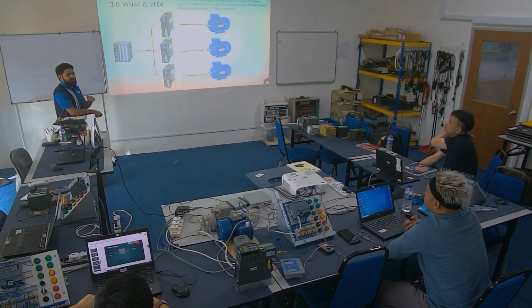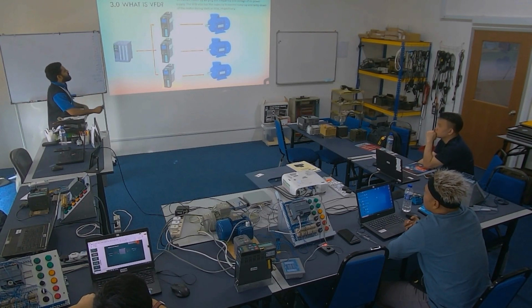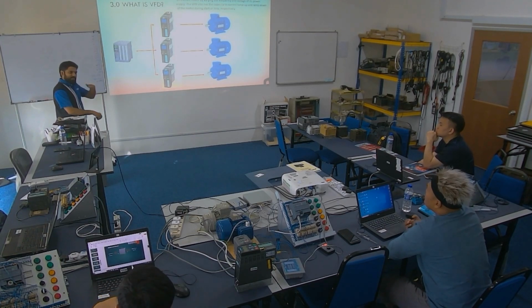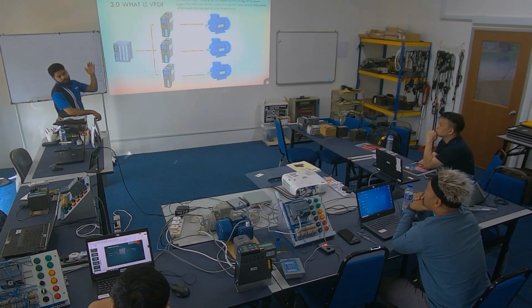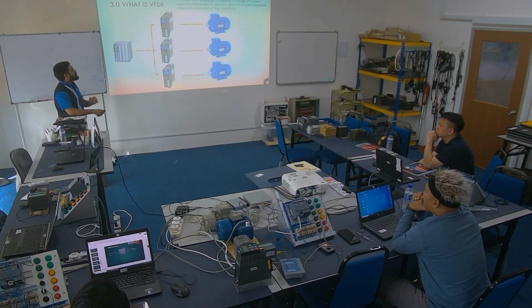If you direct online start, sometimes they use star delta, running on full speed first before changing to star delta. But with a VFD we don't need to do that. We can start at full speed or at a lower speed, because the VFD can control the ramp up and ramp down, meaning we can control the torque as well.